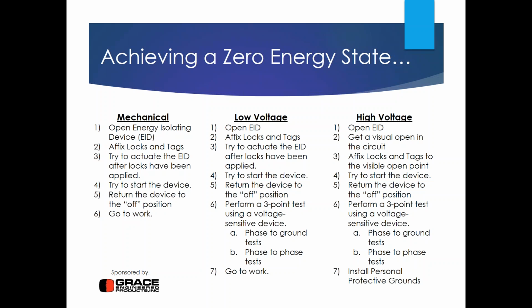Now, if we're changing out that motor, the first 4 steps are the same ones we just covered in the previous column. You're going to do the same thing as you would for mechanical lockout. At low voltage, 600 volts and below, there's only one more requirement, and that is a 3-point test with a sensitive voltage testing device. You can see they want you to test phase to ground and phase to phase. Often this can be done with a voltmeter or in some cases a proximity tester. But this is really where the PESDs stand out, because you don't have to interface with the energized parts, you have a barrier between you and those energized parts, and it also protects against arc flash hazards. I'll leave that to Dan to talk about further. So on low voltage systems, the only requirement in addition to mechanical lockout is a 3-point test with a sensitive voltage testing device.